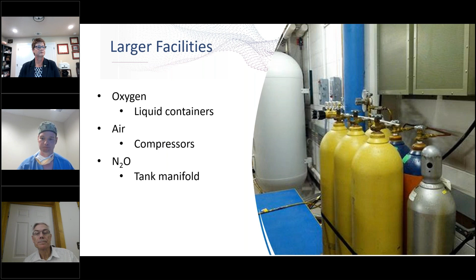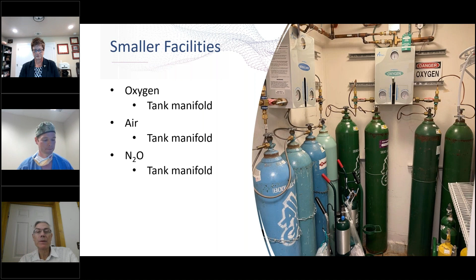For smaller facilities, this is actually a photo from a facility I've worked at before. It's a small two operating room ambulatory surgical center. They generally exclusively use tank manifolds. They will not have a large liquid oxygen tank, and they will not have on-site compressors. They essentially get all their gases through tank manifolds. You notice the blue ones for nitrous oxide here, and the green ones in the back are the oxygen. If you look right in the lower corner, you can see a little yellow tank. They have small E cylinders for medical air at this facility. Next.